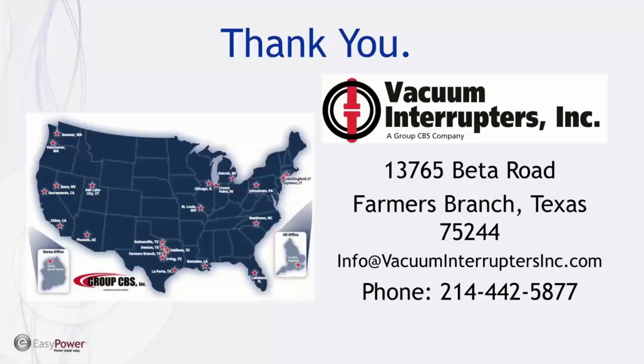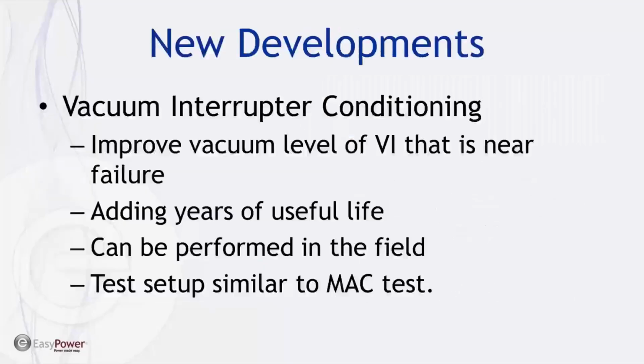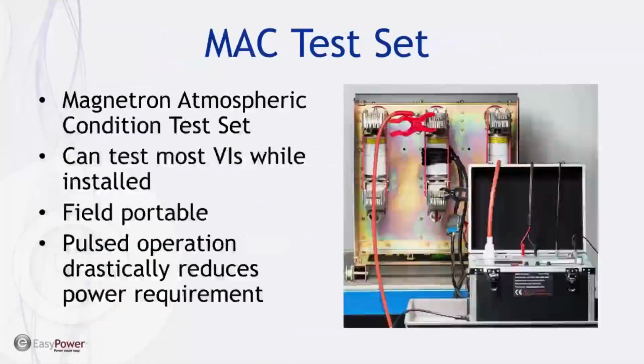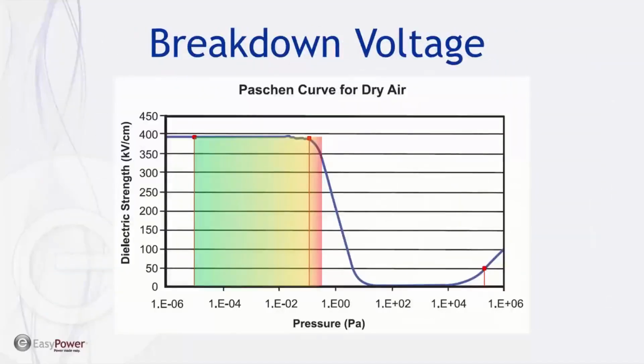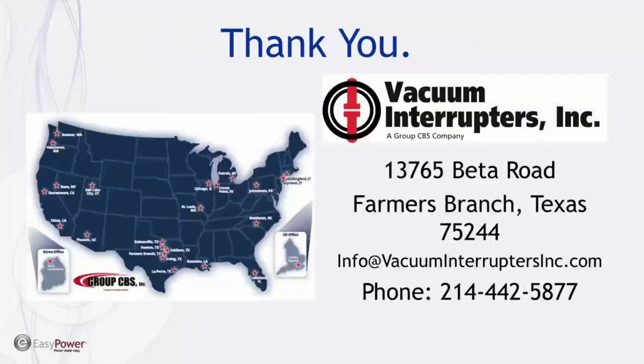The only question that came in, we'll kind of leave it open for a couple minutes, was a verification of the negative pressure that's in a typical vacuum interrupter. You showed a graph. What's the range for the negative pressure? The general range, we're in pascals here, so somewhere between 10⁻¹ Pascal down to 10⁻⁵. So that would be 0.1 Pascal down to 0.00001.